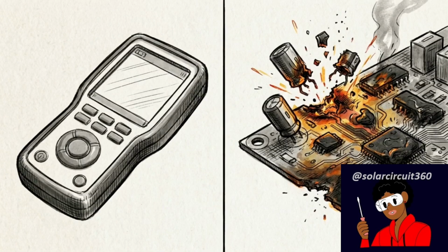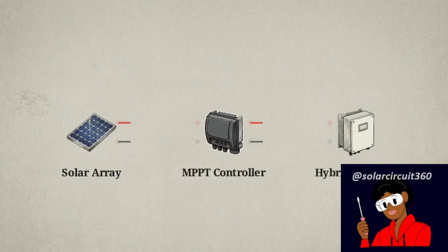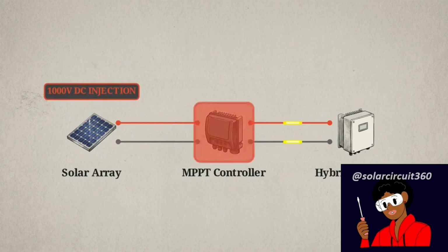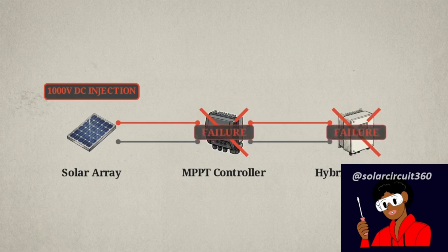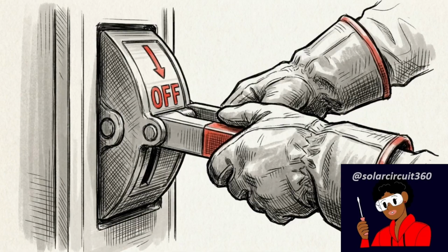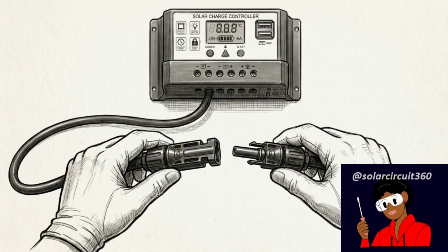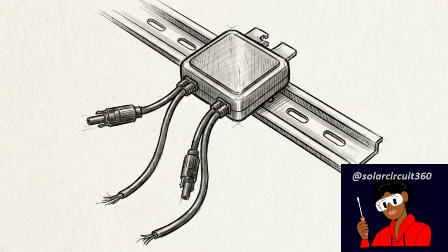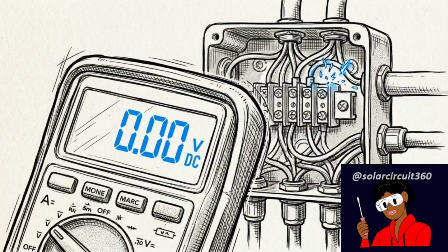While the Megger is a precision diagnostic tool, it can become a destructive force if the solar array isn't properly isolated. Never test live solar conductors or strings still connected to the system architecture. A Megger injects an elevated DC voltage pulse traveling instantly down the line. If this pulse reaches unisolated inverters, it exceeds semiconductor voltage limits, instantly destroying the electronics. The mandatory first step is physical disconnection. Isolate the strings from charge controllers, DC optimizers, and monitoring hardware. Always verify zero voltage with a multimeter before connecting the Megger.